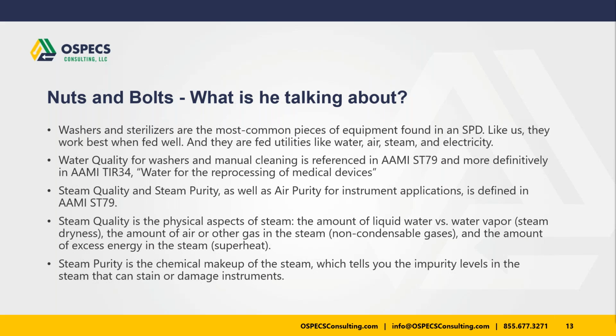Water quality is described in AAMI ST79 and then in more detail in the AAMI TIR34, water for reprocessing medical devices. That document, even as we speak, we're having the first meeting to turn into a standard. So there will be more clarity in how the water you use should be prepared and what it should have in it and what it shouldn't. Steam quality and steam purity, as well as air purity for instrument applications, instrument air, is defined in ST79.